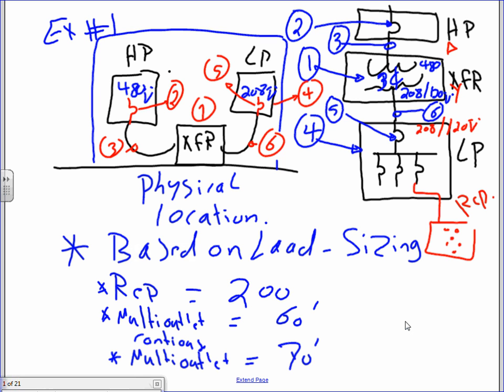Very typical. In the electrical room, Karen, we have something called HP, the high voltage panel, that feeds, this is the panel, that feeds a transformer. Do you guys remember that when we went to the electrical room in Boston? A high voltage panel that feeds a transformer that transforms the voltage from high voltage, which is 480/277, down to 208/120, so we can feed our receptacles. Almost, Derek, every electrical room that you're going to walk in, you're going to have something similar to this. This combo: panel, transformer, panel. Panel, transformer, panel. Did you guys hear me?